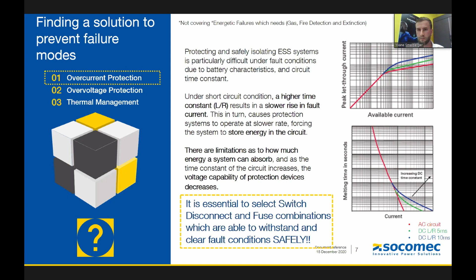So in overcurrent protection, protecting and isolating ESS systems is particularly difficult because of the fault conditions that are caused by the battery characteristics and also the circuit time constants in DC. So under a short circuit condition, a high time constant in the circuit can result in a slower rise in fault current, which means that the protection systems would operate slower, forcing the system to store a lot more energy in the circuit. Now, obviously, there's a limitation as to how much energy can be absorbed in the circuit. And also, as the time constant increases, the voltage capability of my protection device decreases. So it is essential for us to select switch disconnection and fuse combinations in our system that would be able to withstand and clear faults safely.